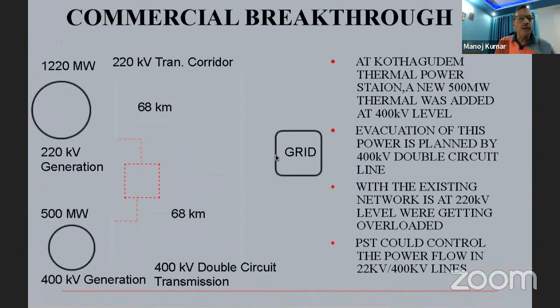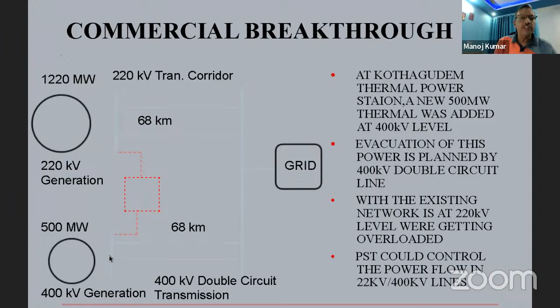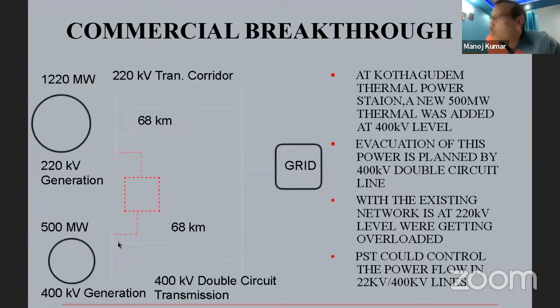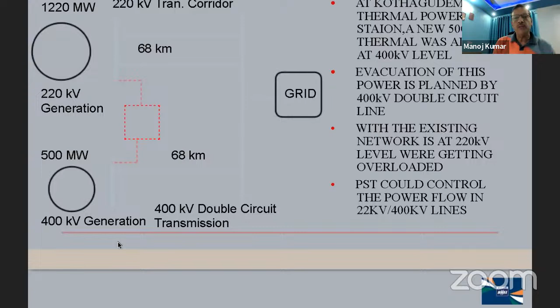BHEL is the only agency in India which has developed this phase shifting transformer, where we can provide a phase shift of plus minus 15 degrees, and we can control roughly 150 megawatt of power transfer from the 220 kV side to the 400 kV side and vice versa. It is working satisfactorily at the Kothagudem station as on date. It was commissioned in 2014. And BHEL is again pioneering, working on 800 kV phase shifting transformers to put into the network.